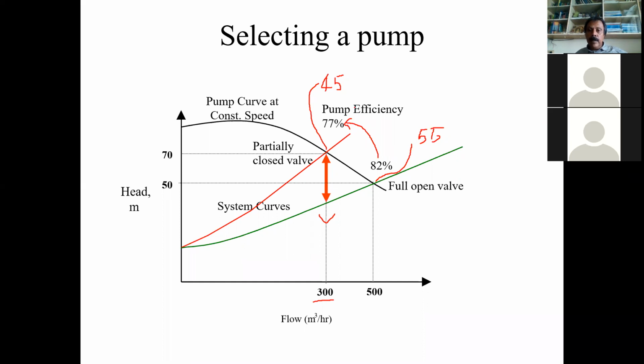How did we get the lower power here? After throttling, it should have increased the power. After reduction in efficiency, it should have increased the power. But then here we are getting a reduced power. This happens because the flow rate has reduced. So as you have seen in the first pump curve, as you increase the flow rate, the power also increases and vice versa. So now it is not against the same flow rate we are comparing. Earlier it was 500 meter cube, 55 kilowatt. Now it is 300 meter cube and it is 45 kilowatt. So it doesn't mean that we have saved energy.